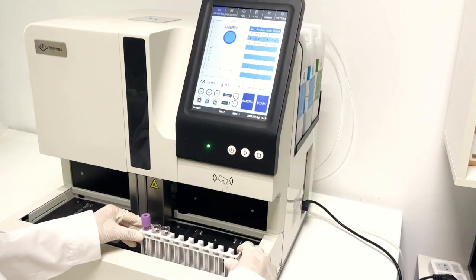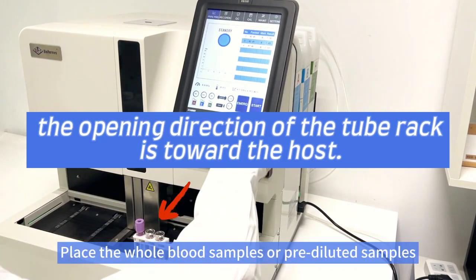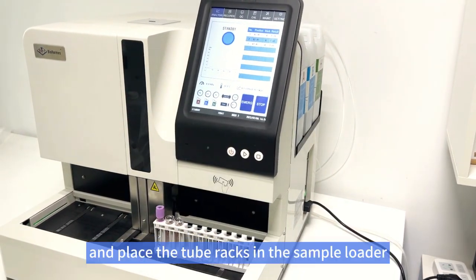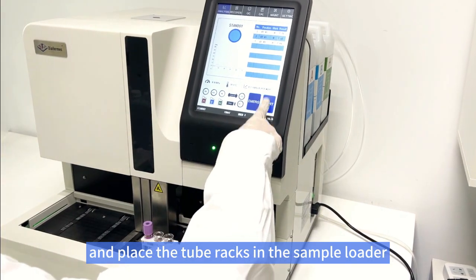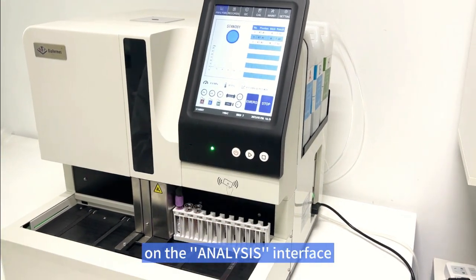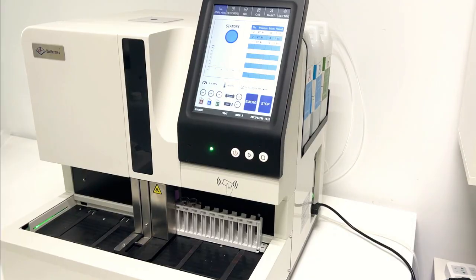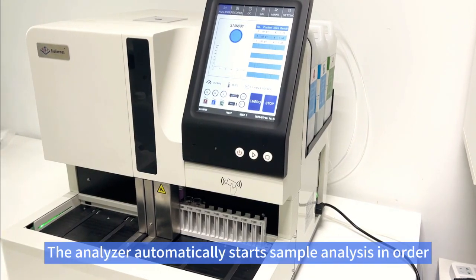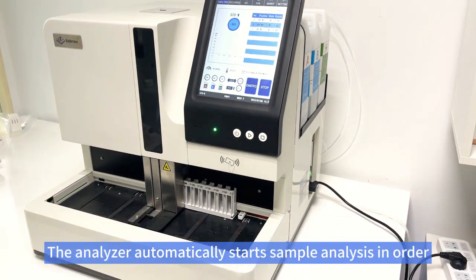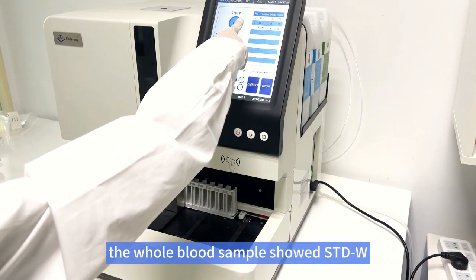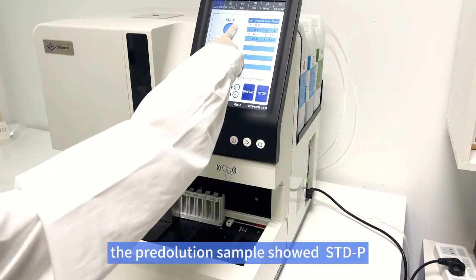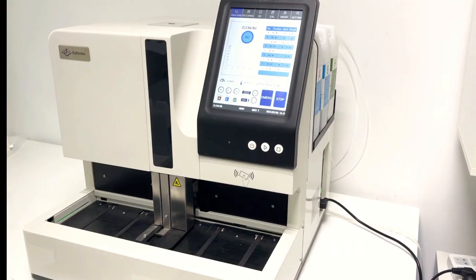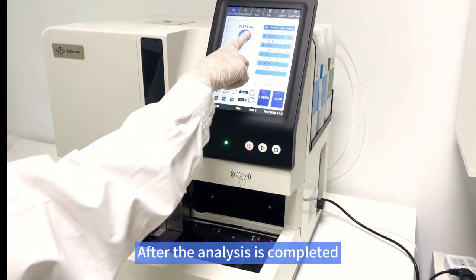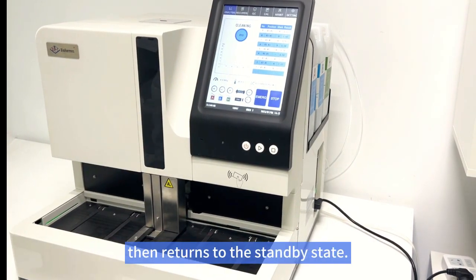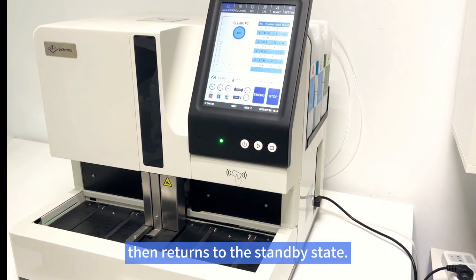Place the whole blood samples or pre-diluted samples on the tube racks and place the tube racks in the sample loader. Click the Start button on the analysis interface. The analyzer automatically starts sample analysis in order. The whole blood sample showed STDW. The pre-dilution sample showed STDP. After the analysis is completed, the analyzer will start automatic cleaning, then return to the standby state.